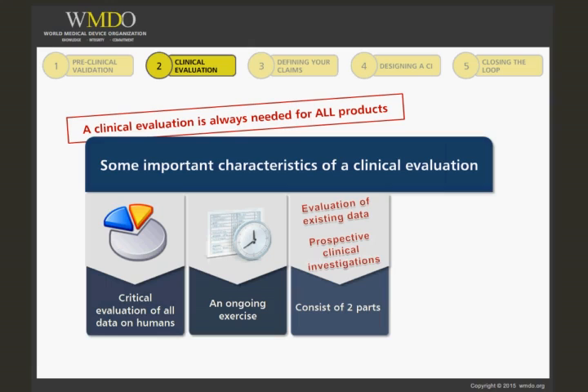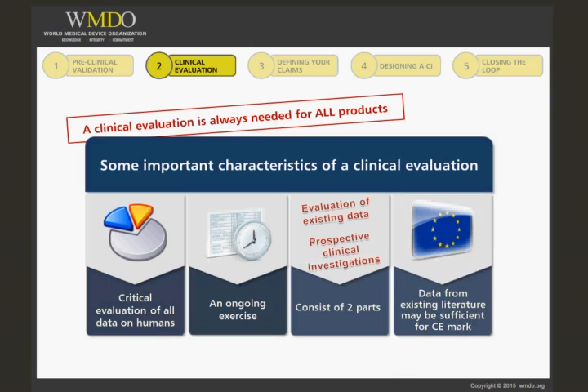Fourth, under the European system, a clinical evaluation based on existing data may be sufficient, provided it supports all the claims made under the CE mark scope.